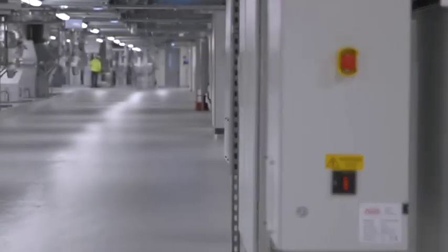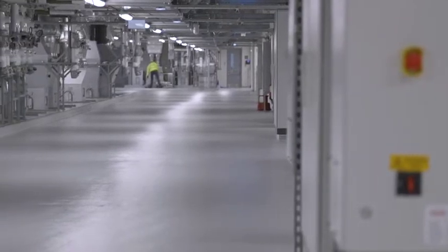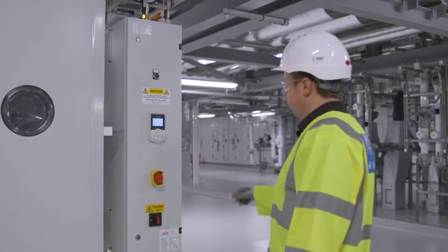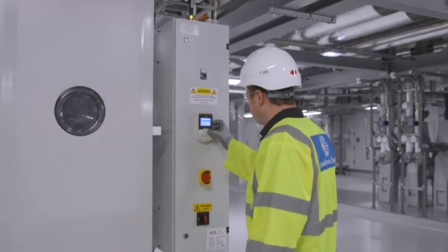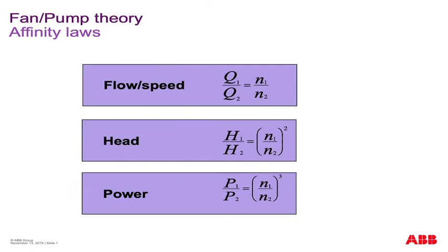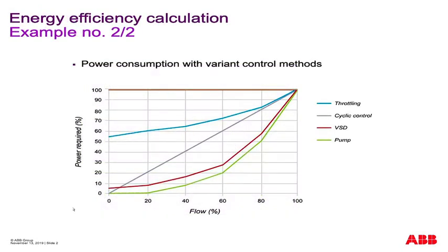At BMS, the dual fan AHU control method ensures that both supply and return fans operate at reduced speed. This is typically 50% of motor nominal speed. For a centrifugal fan application, this takes full advantage of the Affinity Law of physics. The power absorbed by the load is proportional to speed to the power of 3. This represents a power saving of up to 80% in many applications. This relationship between power and speed can be applied to centrifugal fans or pumps.